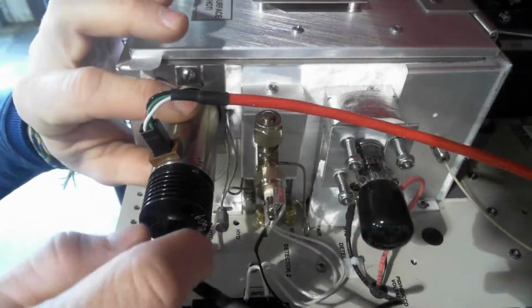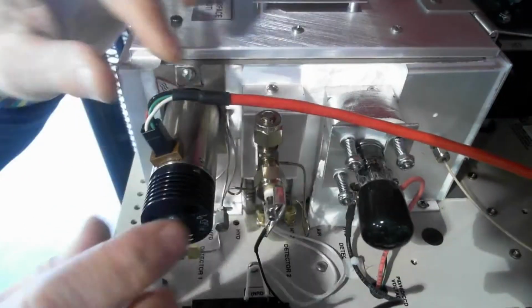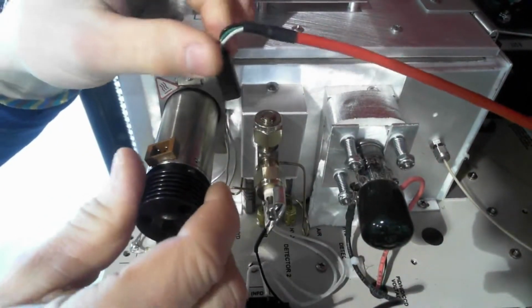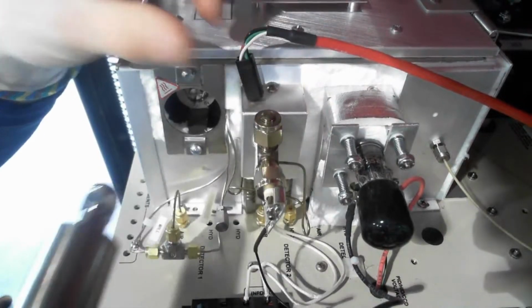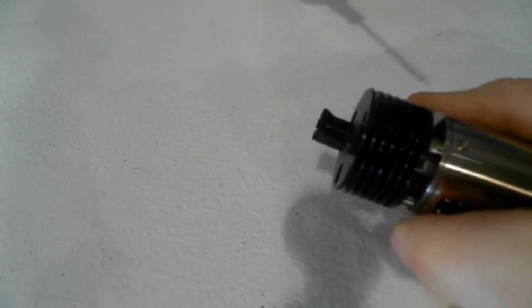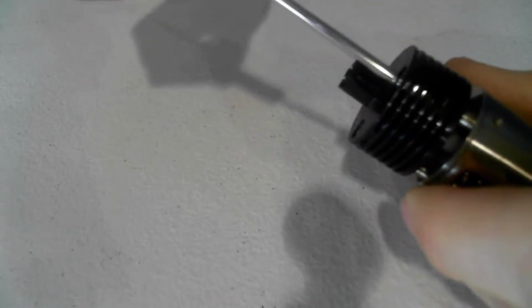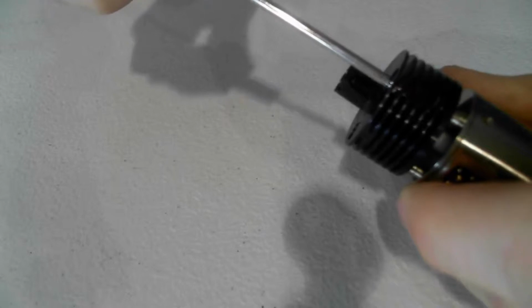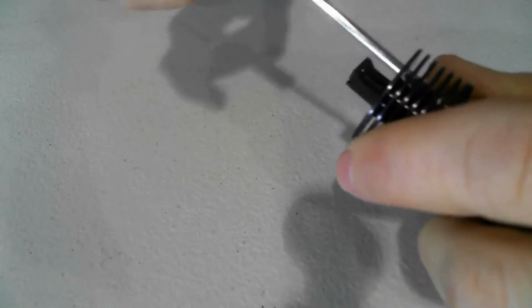Once cooled, you will want to remove the XSD signal cable and the heater cable, twist the cell toward you, and pull away from the GC. Once the XSD is removed from the GC, we can remove the 3 screws that hold the upper probe assembly section in place. This is done by using a small slot drive screwdriver.